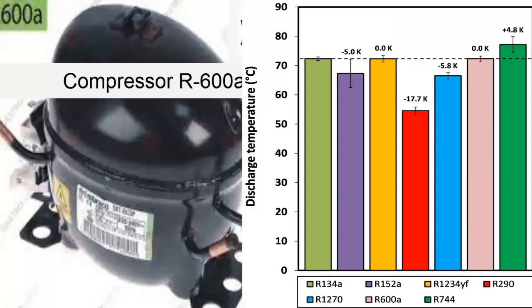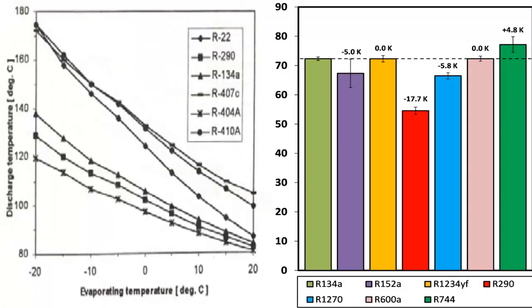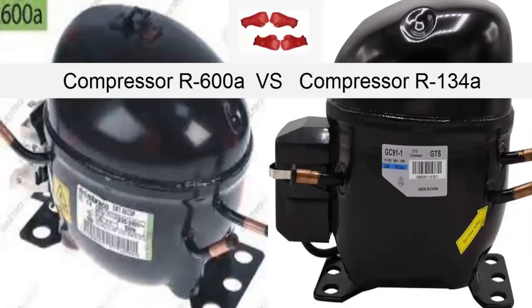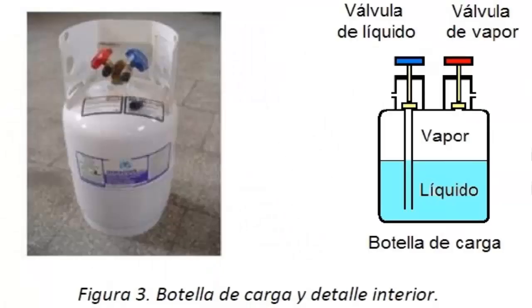As for the temperature at the compressor outlet, it is observed that practically both discharge temperatures are equal. Both the R600A compressor and the R134A compressor can be charged in both liquid and vapor phases without problems.